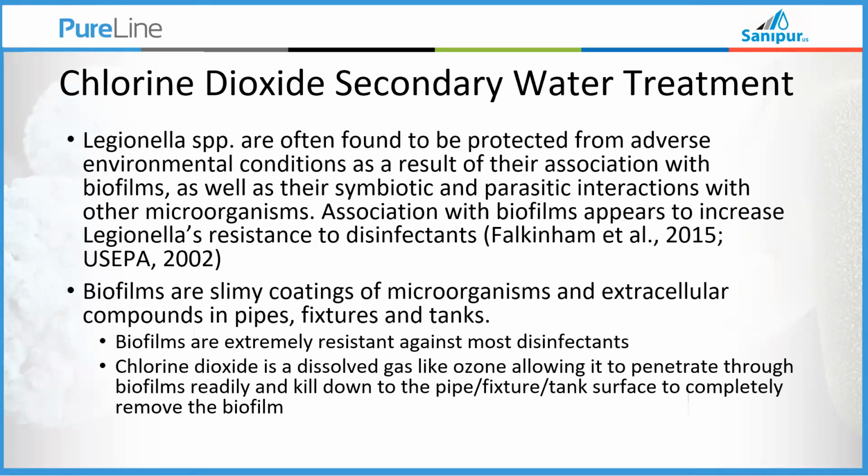its penetration through the biofilm layer is almost unparalleled and will attack it all the way to the surface of the pipe, killing everything, including the interstitial bacteria, which are holding that biofilm to the pipe, which eventually then allows it to flush everything out of the system, leaving little to nothing behind. And biofilms often can be seen, very often felt, and it's a thin, slimy residue on the insides of pipes and fittings in the water systems that you have.